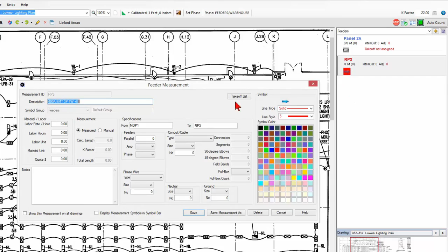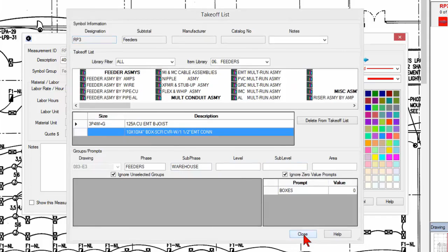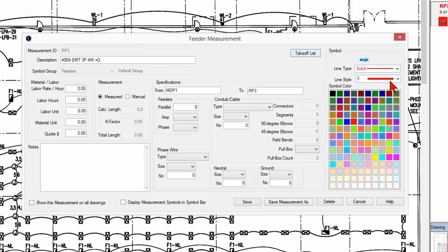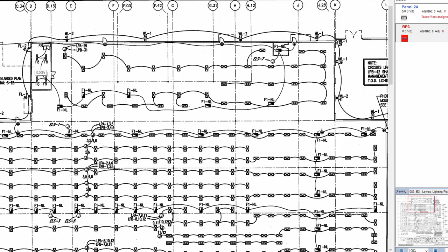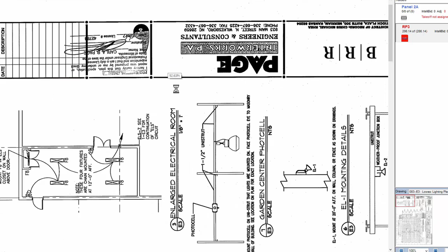And again, with the integration with IntelliBid, I went into the materials database and found an assembly that's a 125 amp copper feeder, and I'm going to put in a 10 by 10 pull box here, if I need it, if I go over 100 feet and so forth, which I know I'm going to. So I've also got the color that I chose to draw the line on the drawing, and simply hit select, save. And to draw the measurement, I'm simply going to click and point and follow where I make my pathway, and everywhere I change direction, which is right there, I click. And then I click again where I want to end up, and right there in the middle I've actually needed to put a pull box at around the 92 foot mark. So I've got 206 feet on the feeder.